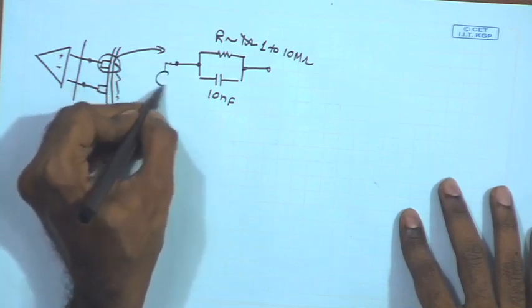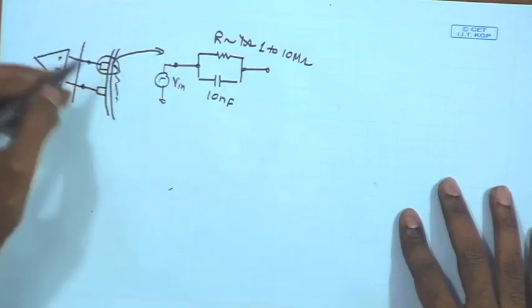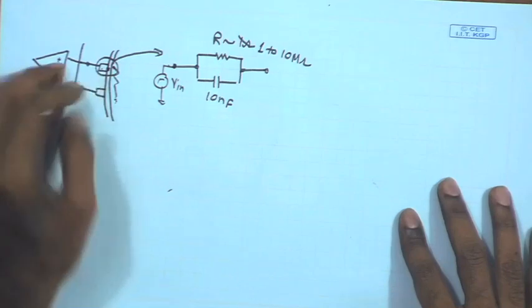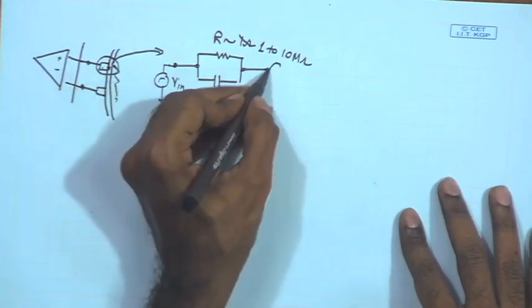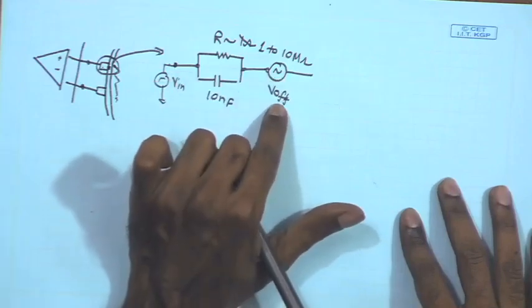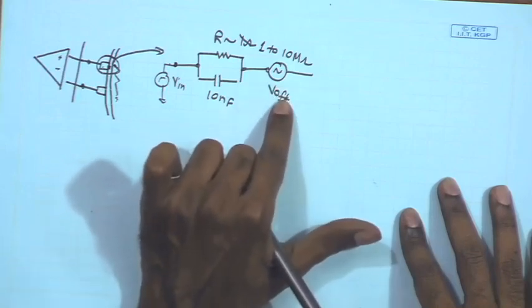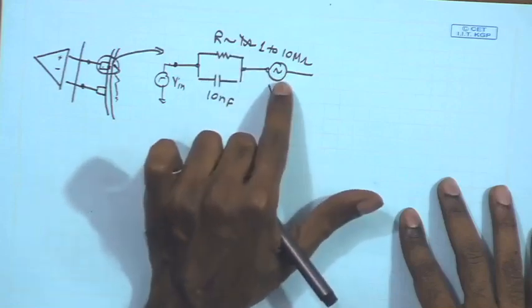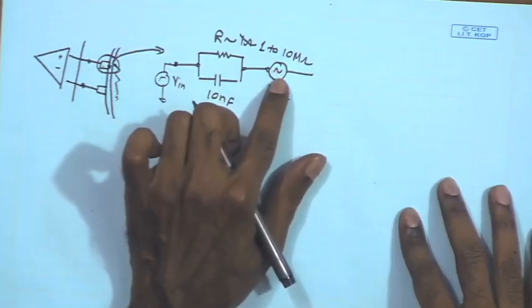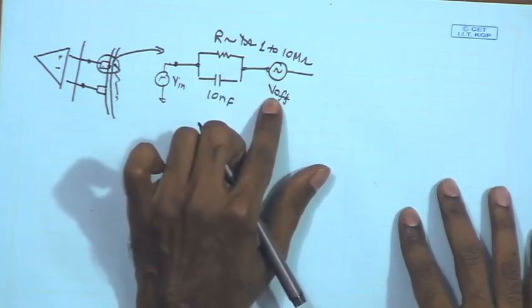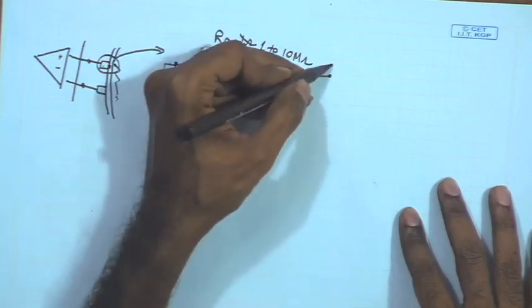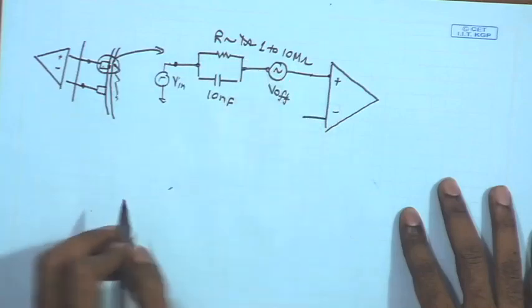We next need to look into the model of this electrode. In general, these electrodes can be modeled as a parallel combination of a resistor and capacitor. For a standard dry electrode that has been properly used in literature, the R values will be in the order of megaohms — it can be all the way to tens of megaohms — and the capacitor values can be in the range of nanofarads. At the interface of the electrode and the skin there can be a time-varying potential because of defects or artifacts at the interface, modeled as a time-varying signal called V_offset, which is a property of the electrode-skin interface. This is not a desired signal, but it can be much larger in magnitude and can overwhelm your desired signal.